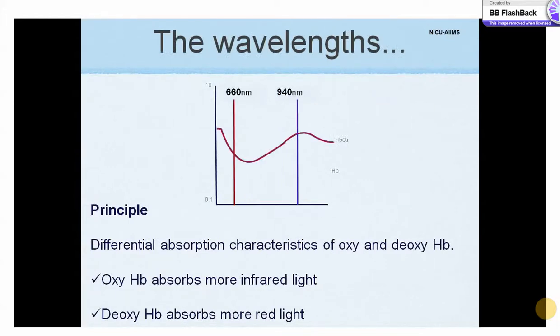The principle of pulse oximetry is based on the differential absorption characteristics of oxygenated — that is red — and deoxygenated — that is dark — hemoglobin. Oxygenated hemoglobin absorbs more infrared light, allowing more red light to pass through, whereas deoxygenated hemoglobin absorbs more red light, allowing more infrared light to pass through.